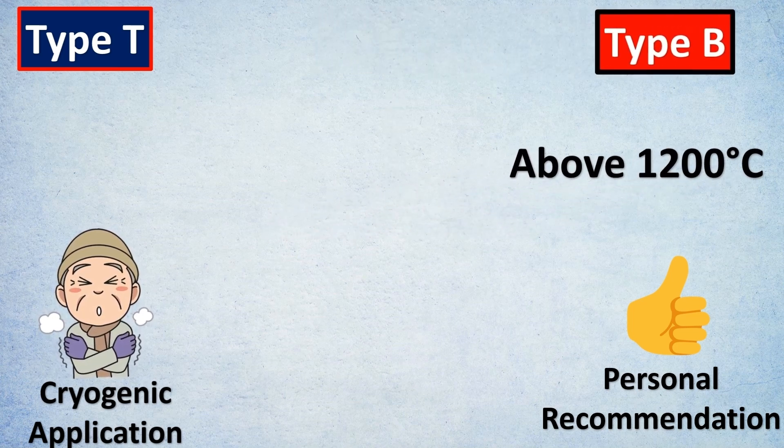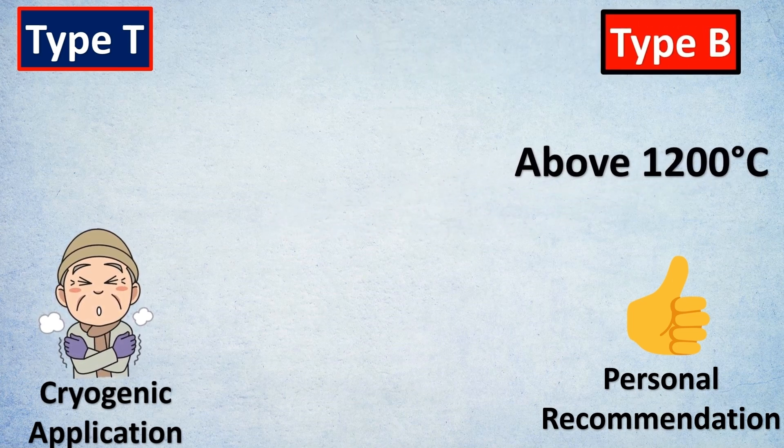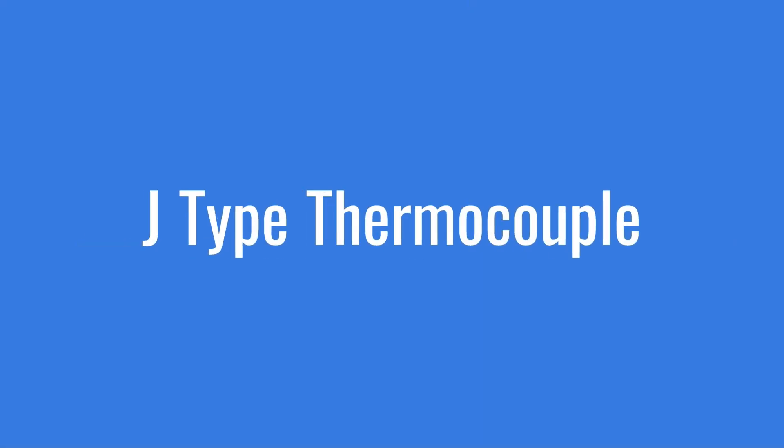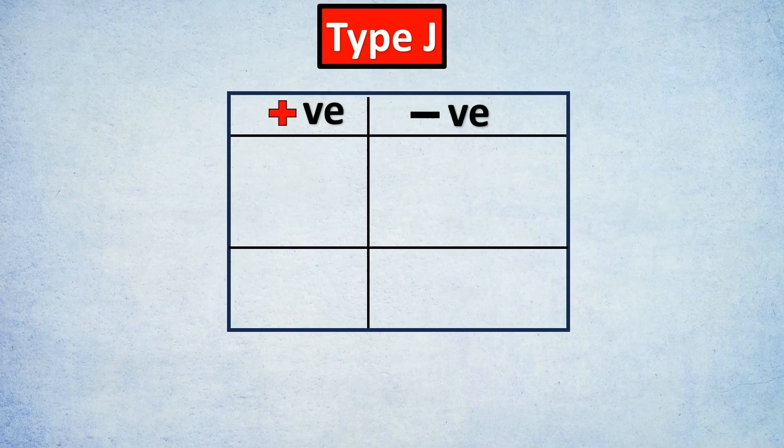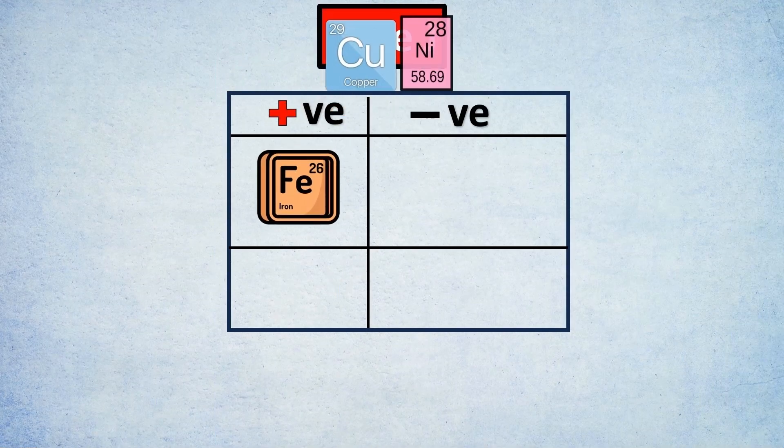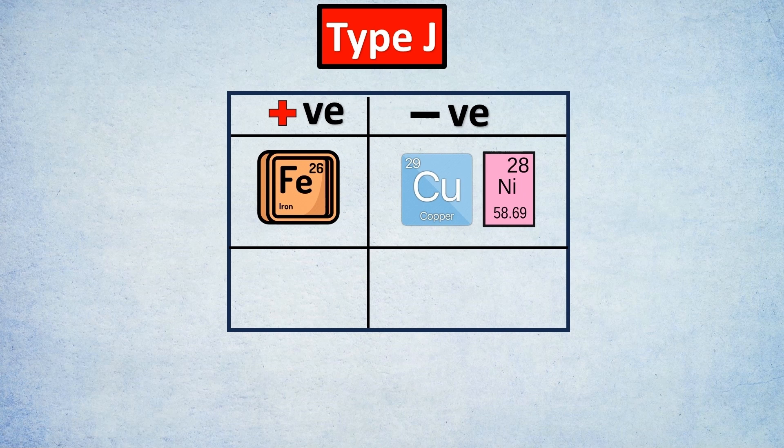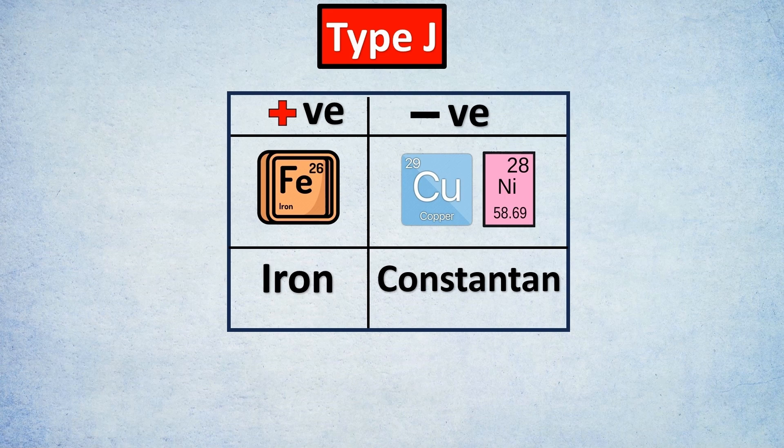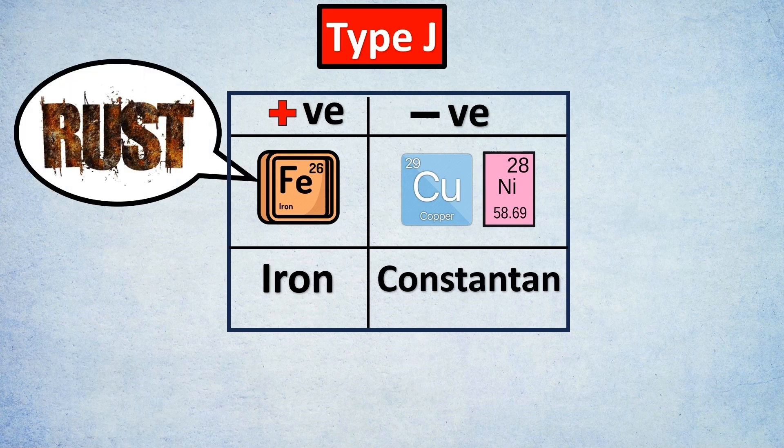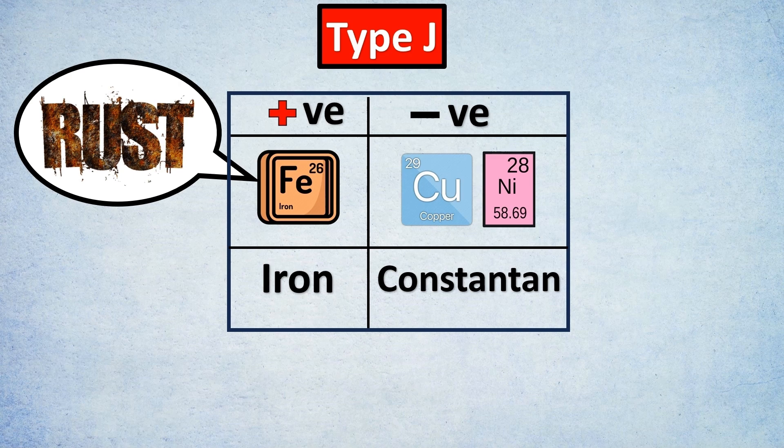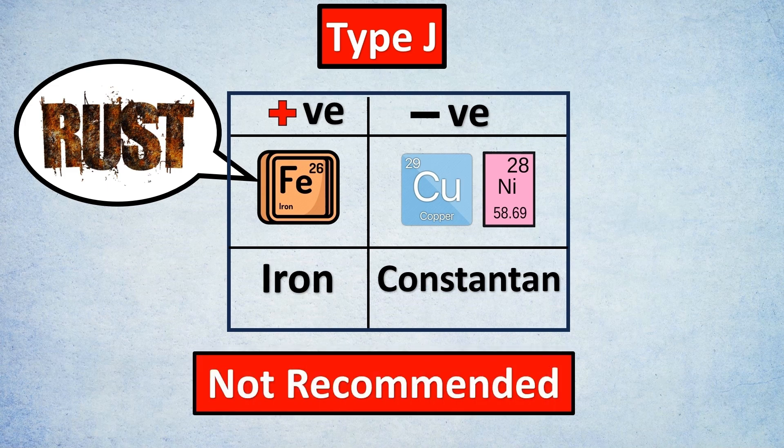One of the most important parts is Type J thermocouples. Type J has the positive section with iron and the negative section with constantan, which is copper and nickel. Remember that iron is very prone to rusting. As per API RP recommendation, this should be a legacy choice. Only if there's absolutely no choice available; otherwise, keep this as a non-recommended choice for majority of project applications.